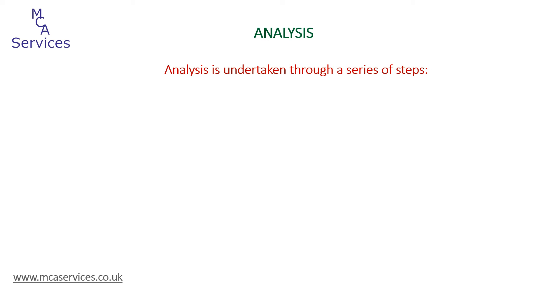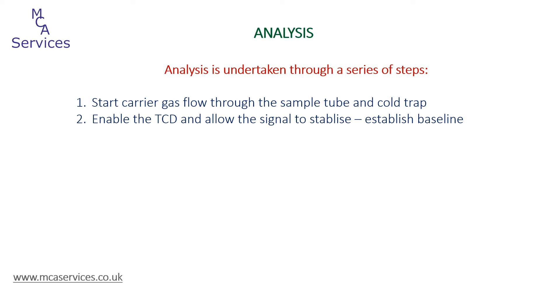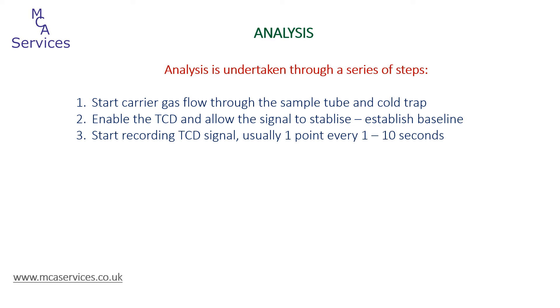Analysis is undertaken following a series of pre-programmed steps to form an experiment. A typical procedure for temperature programmed reduction, oxidation, or decomposition follows the same common steps. The flow of carrier gas is started so that the analysis stream passes through the sample, through the cold trap, and onto the TCD. The TCD is then enabled and the signal is allowed to stabilise to form a baseline. We then start recording the TCD signal — typically one point every one to ten seconds, depending on the duration of the analysis. We then start to heat the sample; a good starting ramp rate is around about 10 degrees C per minute, but again that can be varied.